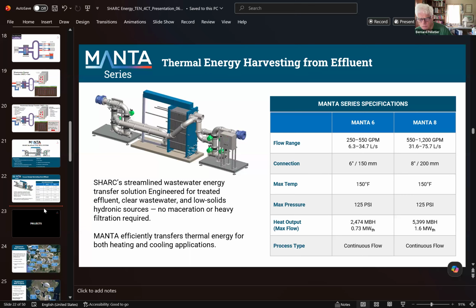One question: when you're rejecting heat, say from a data center or elsewhere, what's the upper limit to the temperature that you're sending out? In other words, is it scalding water? Is it going to have some adverse effect? Yeah, so do no harm is our first rule of thumb, and we are always driven by the local municipality. So when you're connecting to a municipal sewer line, right?